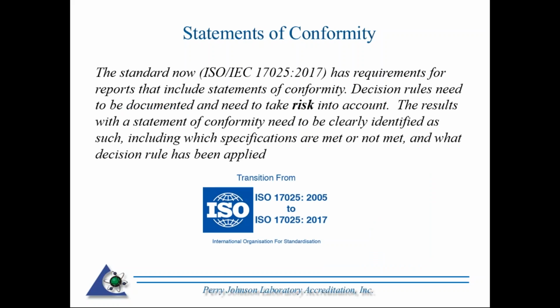So we're going to look at today's topic, statements of conformity. We are referring to the 2017 17025 standard, and we're in a transition over the next several years because folks are in the process of transitioning from 2005 to 2017. The 2017 version has requirements for reports that include statements of conformity. Decision rules need to be documented and need to take risk into account. I highlighted that word risk because it appears frequently in the 2017 standard. The results with a statement of conformity need to be clearly identified as such, including which specifications are met or not met, and what decision rule has been applied.